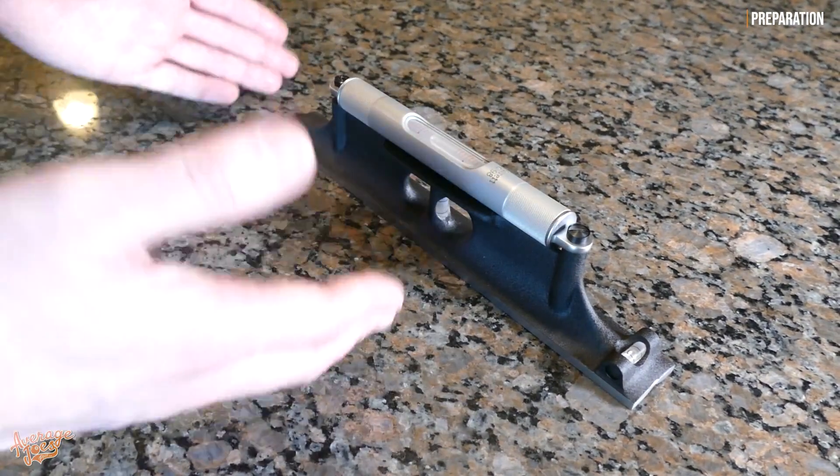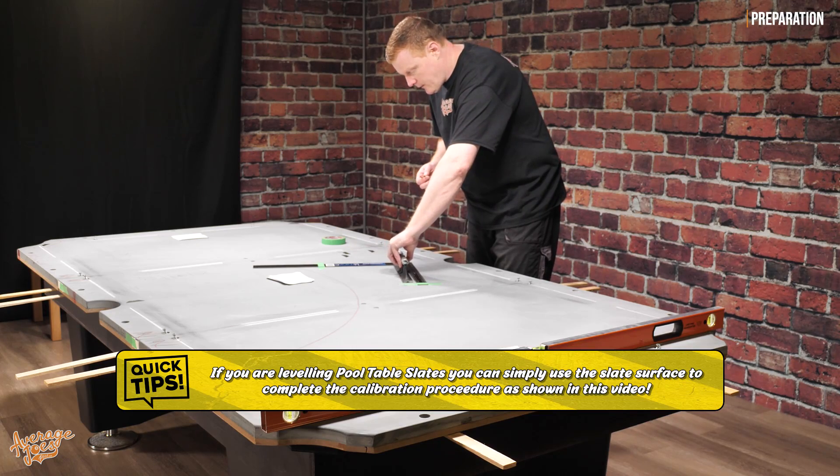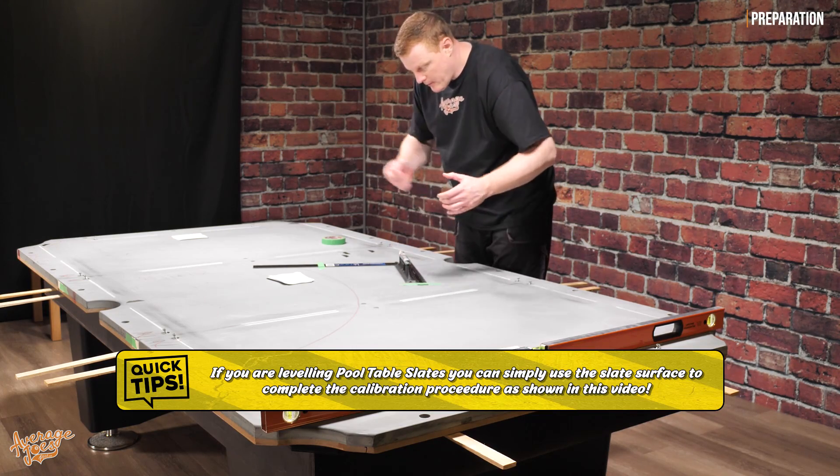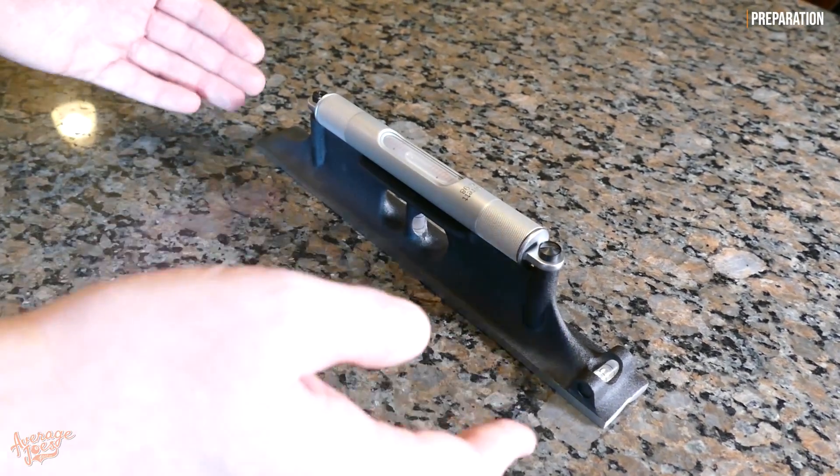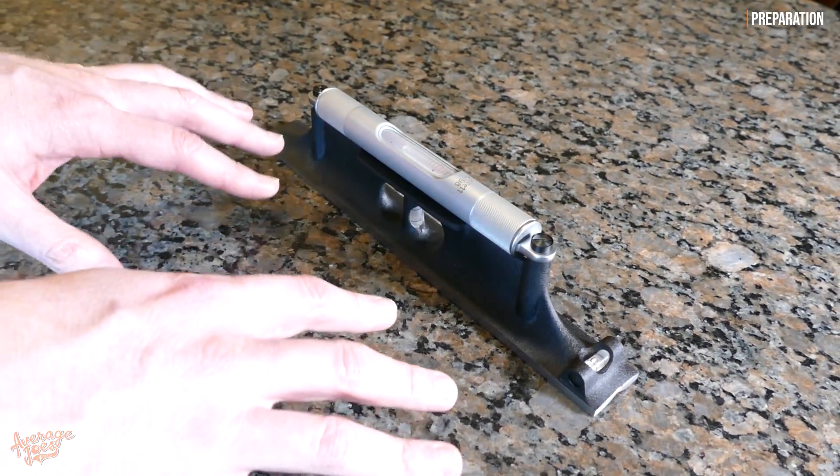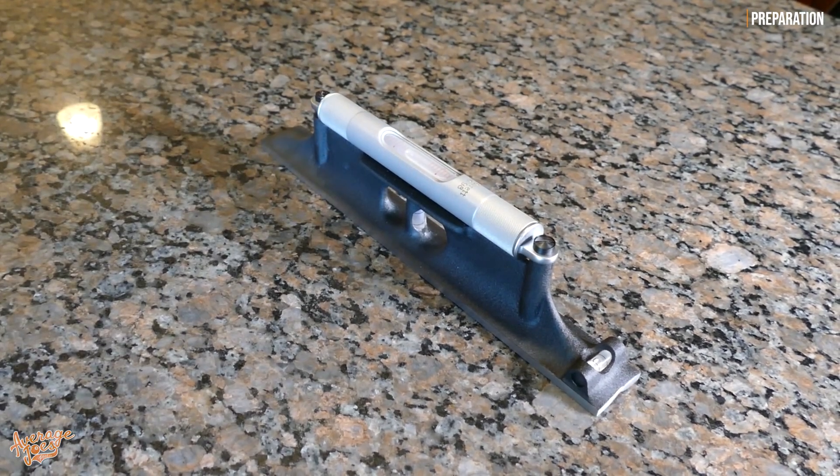Ideally you want something machined like our granite worktop here, or if you've got a steel workbench, something like that is also ideal. But you don't want to be trying to calibrate something like this using something that has flexibility in it, such as wood. So make sure you have a nice solid and flat surface. Remember it doesn't have to be level.